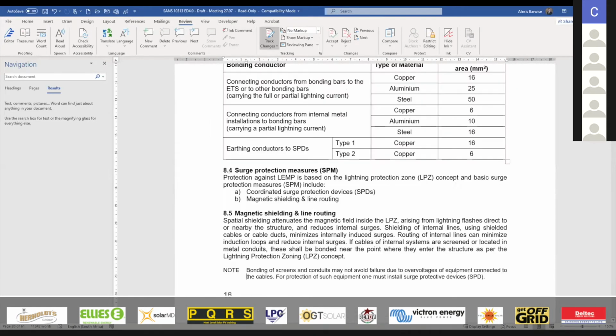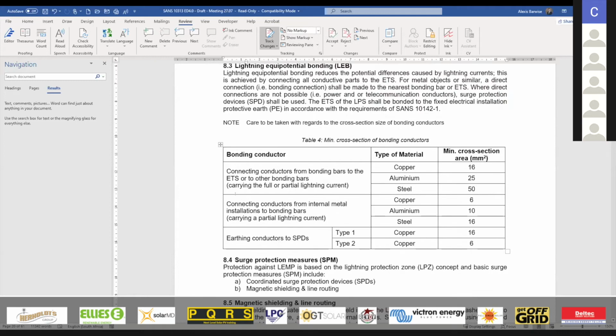So if you are doing the earthing connection, so the bonding conductors, if it's copper, 16 mm² when considering lightning currents. When we're not considering lightning currents, 6 mm² when it's copper. Aluminium, just obviously size up. And even here on the SPDs, if you're installing a type 1, it will be 16 mm². And if you're installing a type 2, again 6 mm², because type 2s are taking care of induced lightning, so just not direct strikes.